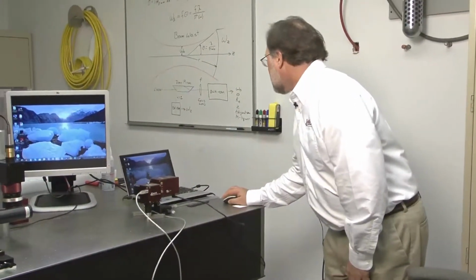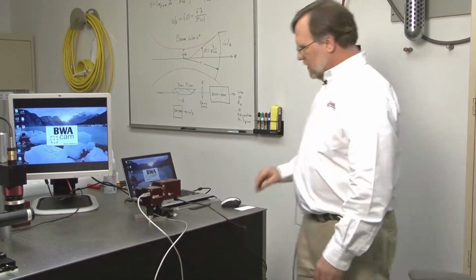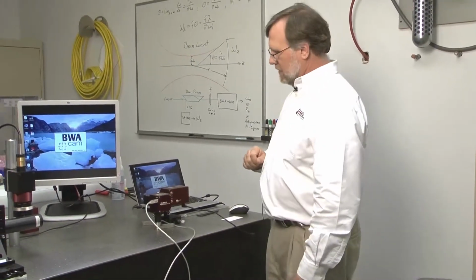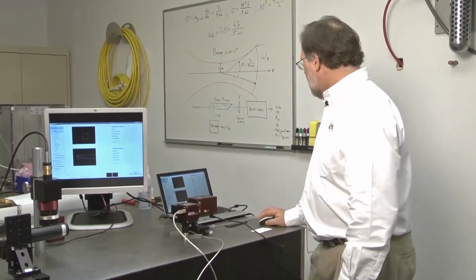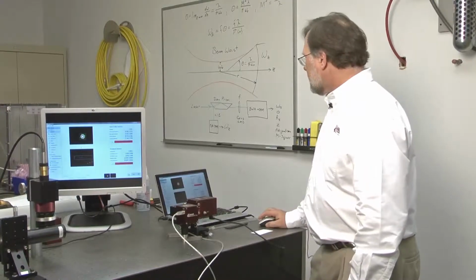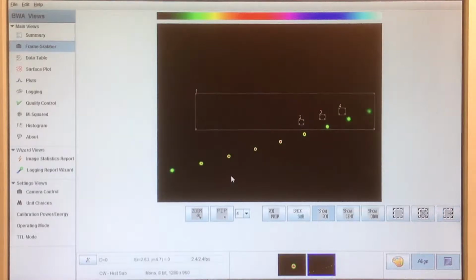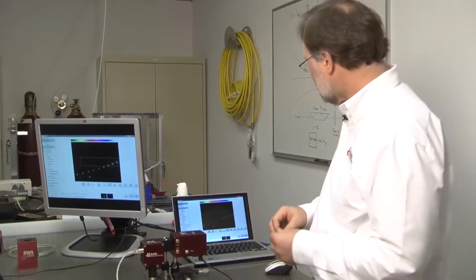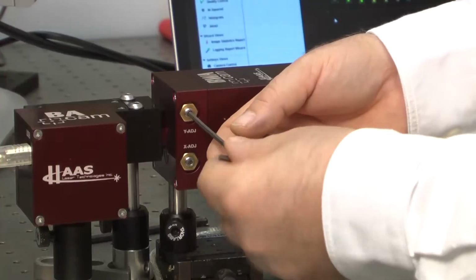I will now turn on the software and make a few adjustments. The camera is factory aligned, but there are probably a few adjustments that have to be made. Hit the play button, and I need to go to the frame grabber and look at the beam waist analyzer camera. So here we see the various spatial, time delayed slices of the beam waist, and I need to do a little bit of adjustment here to get it on the screen, which I'll do right here.